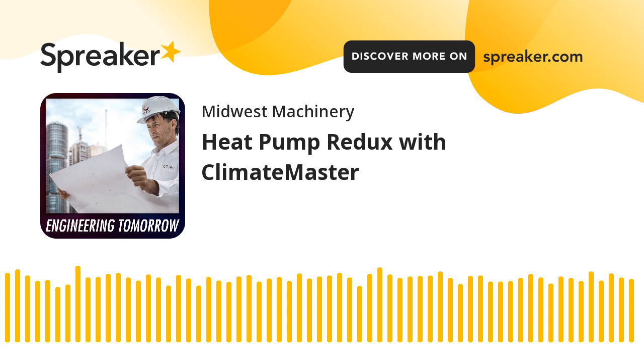In the summer mode, we're rejecting heat into the ground, and we're also using the cooling tower to reject heat. And then in the winter operation, again, we don't have a boiler. So we remove the installation of a boiler, the maintenance of a boiler, and the space required in a mechanical room for the boiler as well. We're using that ground thermal energy for all of our heat in the system, because we size that ground loop to only handle the heat requirement in the building.